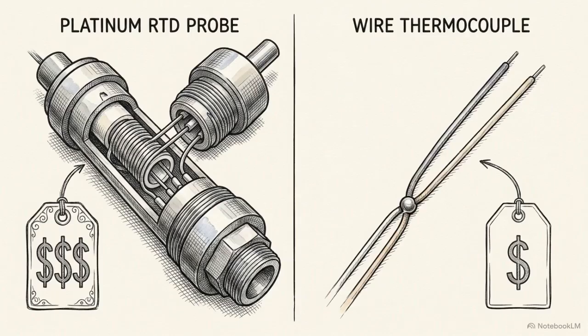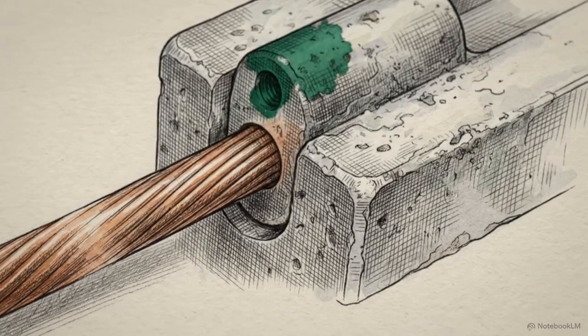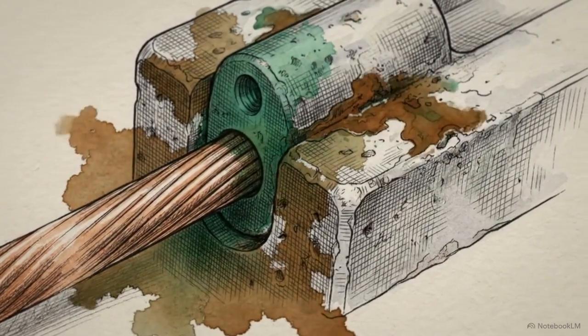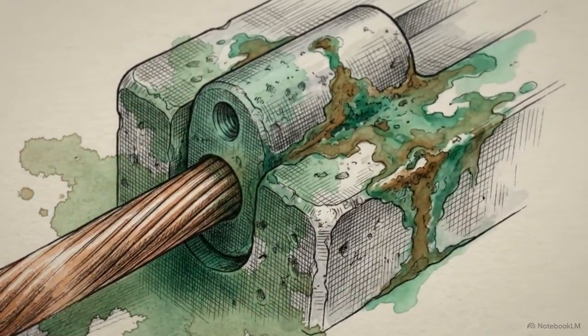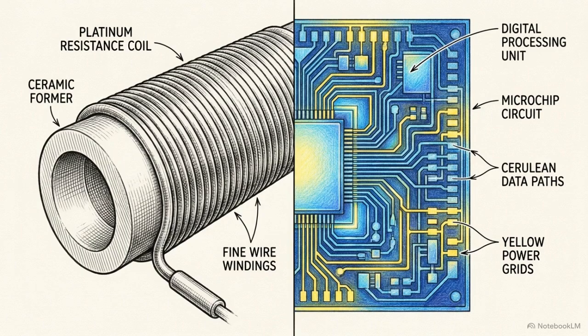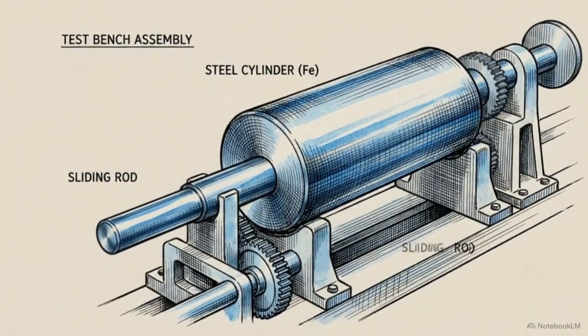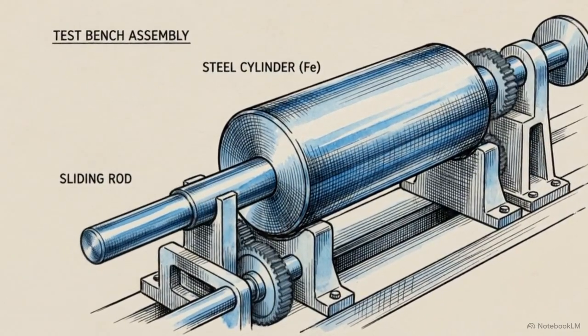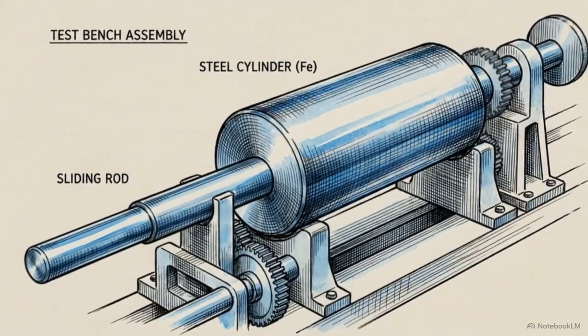This high precision comes with operational trade-offs. The reliance on pure platinum makes RTDs significantly more expensive than alternatives like standard thermocouples. Because the unit tracks tiny fractions of resistance, even minor corrosion or a slightly loose wire connection will introduce massive data errors. An RTD illustrates the transducer pipeline precisely, a passive physical material made useful only by a highly sensitive, mathematically balanced external circuit. To measure spatial linear displacement rather than temperature, engineers use a completely different mechanism, the linear variable differential transformer, or LVDT.